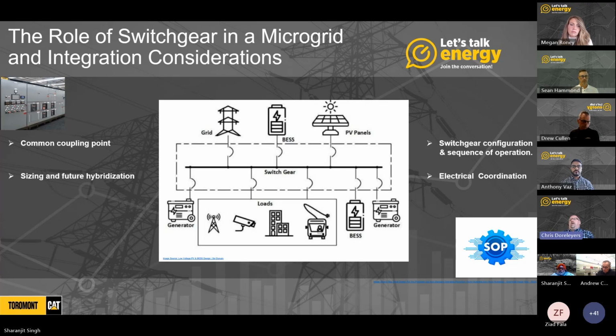The switchgear and the high-level system control sequence for a microgrid should always be reviewed at the same time. Many times, the switchgear and automation may not deliver optimum system performance when evaluated separately. So the key is to evaluate the core switchgear component along with the automation requirements. Ultimately, scalability and future-proofing starts here at the switchgear.